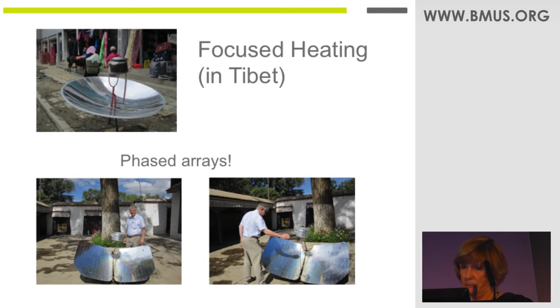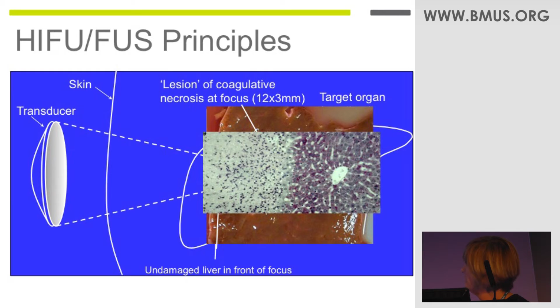It might be a single element focused bowl, or it might be a multi-element phased array. We use that to focus the ultrasound energy at depth within tissue. So here, schematically, we've got the liver, we've got a tumour in the liver, and this is the focal region. And if we turn the power up high enough, sorry, this is the beam plot for the physicists amongst you, so that you only get significant energy in the focus.